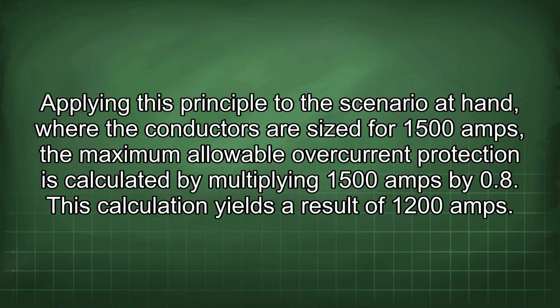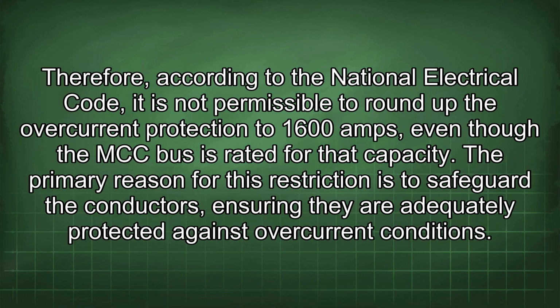Applying this principle to the scenario at hand, where the conductors are sized for 1500 amps, the maximum allowable overcurrent protection is calculated by multiplying 1500 amps by 0.8. This calculation yields a result of 1200 amps. Therefore, according to the National Electrical Code, it is not permissible to round up the overcurrent protection to 1600 amps, even though the MCC bus is rated for that capacity. The primary reason for this restriction is to safeguard the conductors, ensuring they are adequately protected against overcurrent conditions.